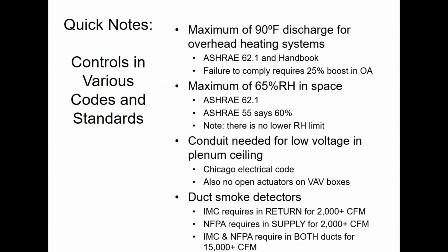Duct smoke detectors, our last topic here. Whenever you have a 2000 CFM system or larger, chances are very high you need a duct smoke detector. Almost every code requires it. International Mechanical Code and pretty much all of the local codes that piggyback off of that would require it. IMC requires it in the return duct when it's above 2000 CFM. If you are following NFPA, National Fire Protection Association, then it's required in the supply duct. If your municipality is following both NFPA and IMC, then you'd have to put 2 duct detectors in, 1 on the supply and 1 on the return.